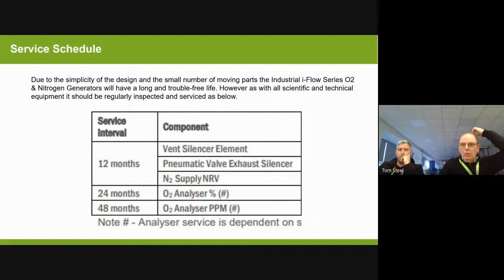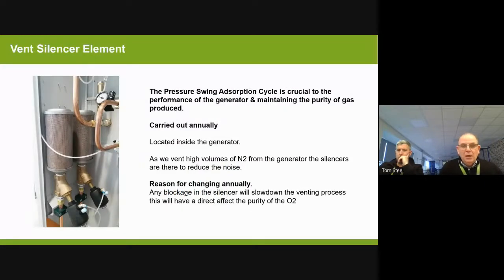So we're going to look at some of the things that will be done in our yearly service. We'll look at the silencers, we're going to look at the valves, and then we'll look at whether you have an O2 analyzer on it. O2 analyzer percentage will be probably what you will require, and that has to be serviced every 24 months as well.